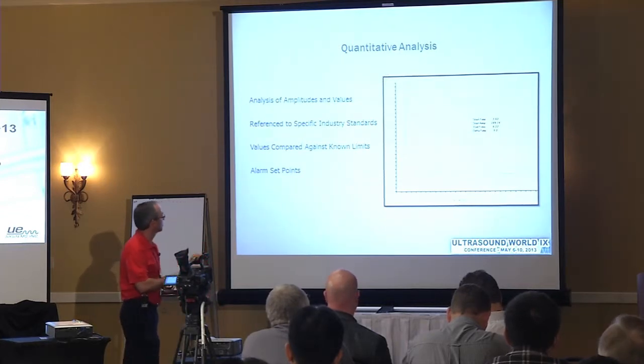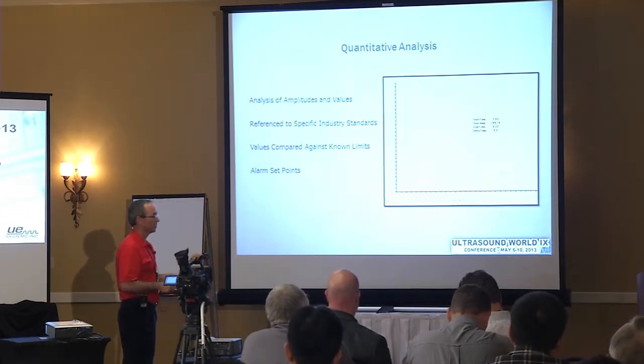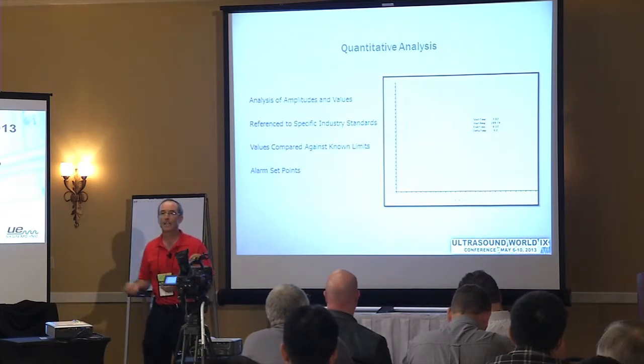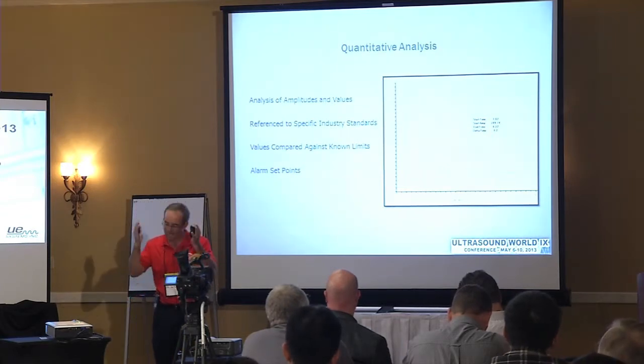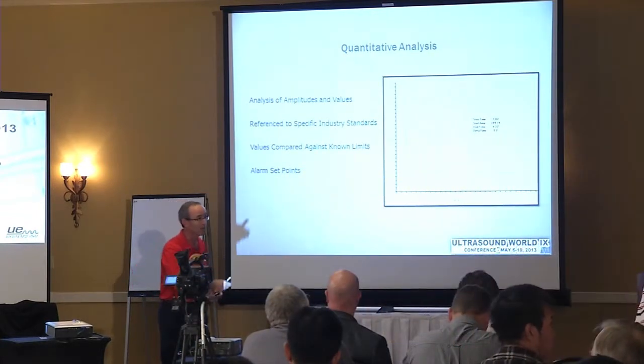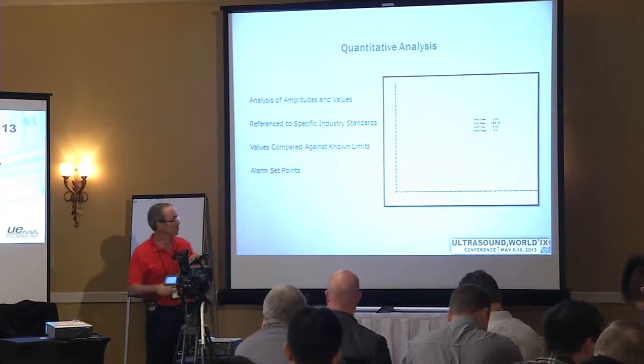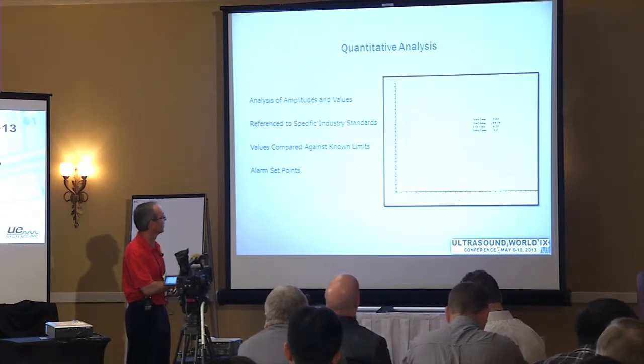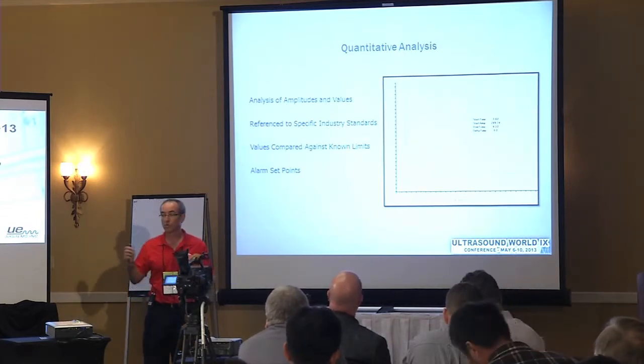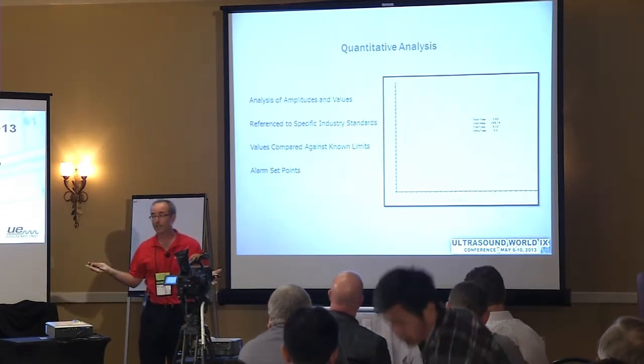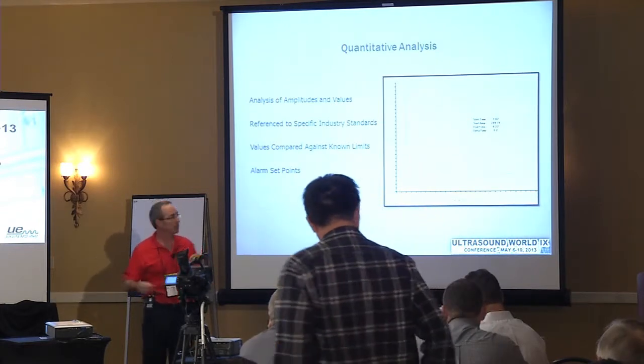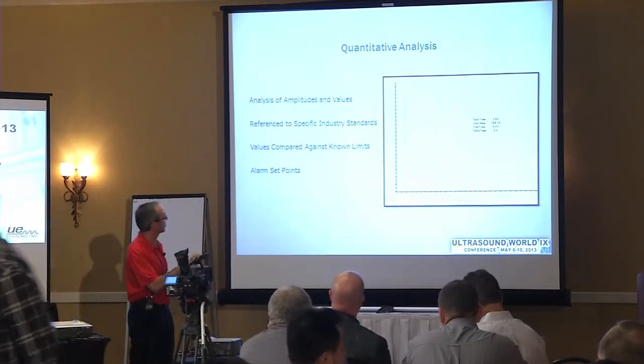So in this situation, we're seeing what we call an inrush startup — a current that's captured through the inrush. If you've ever heard me talk about our technology, I love that inrush startup. Right at the beginning of life, and as we talked about during the break, that inrush startup is everything, because you can base a lot of changes on this. If six months later you're going through the same startup, guess what — it should be exactly the same. The only thing that's going to change, even with a load change, is this part right here.